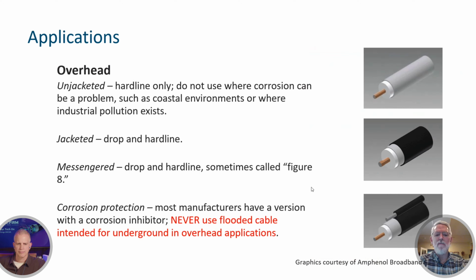Now, corrosion protection. Most, if not all, manufacturers have versions of cable with corrosion inhibitor used for overhead applications or in indoor applications or on the house applications. There's also flooding compound used for cables in underground application. Never use flooded cable that's intended for underground applications in overhead applications. Don't do it. Guess what happens if you use it in overhead applications? Flooding compound will eventually drip out, and if it drips on somebody's car parked on the street, not good. Messy stuff.